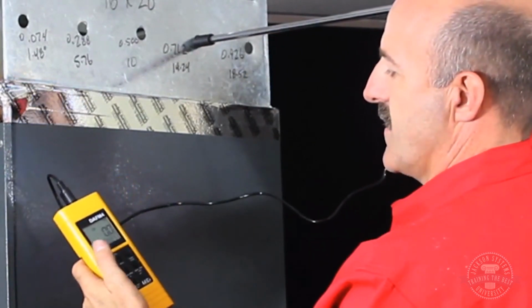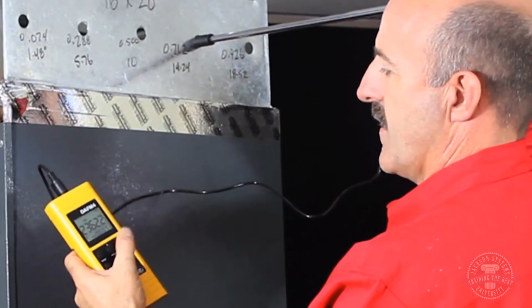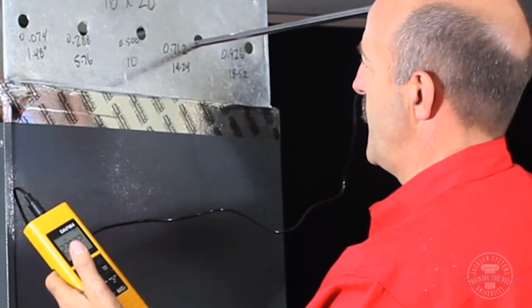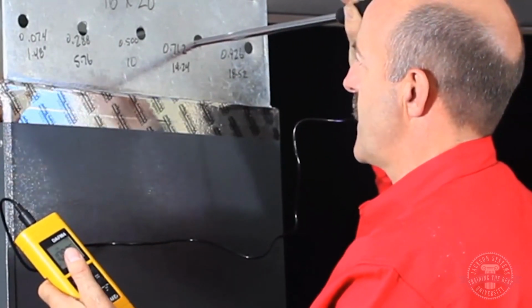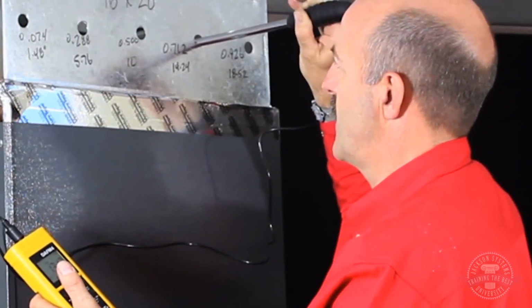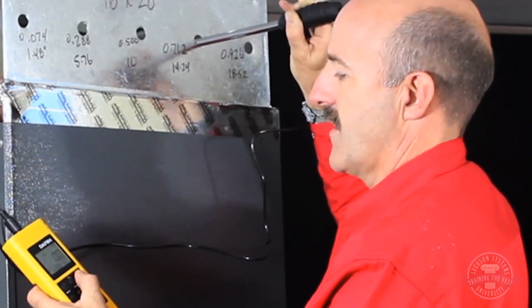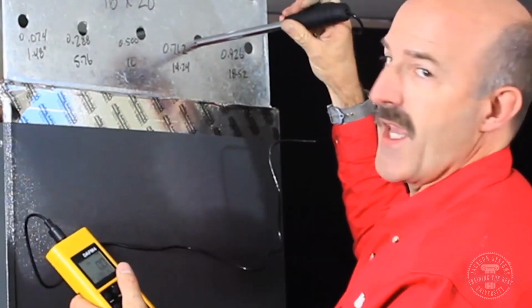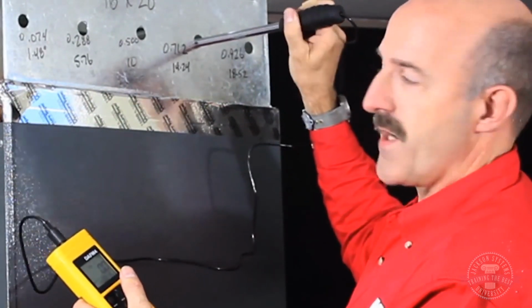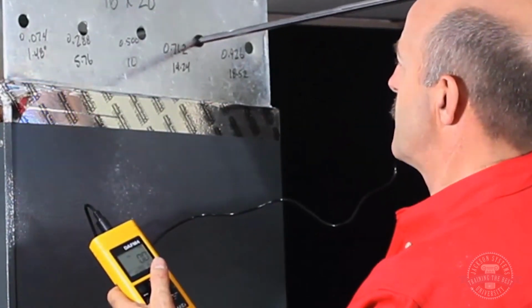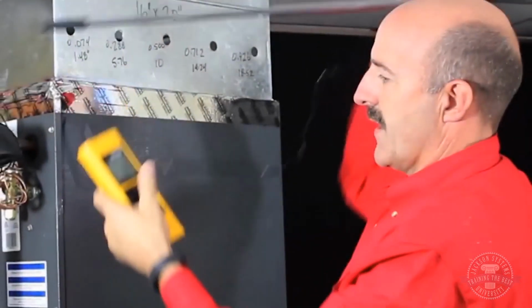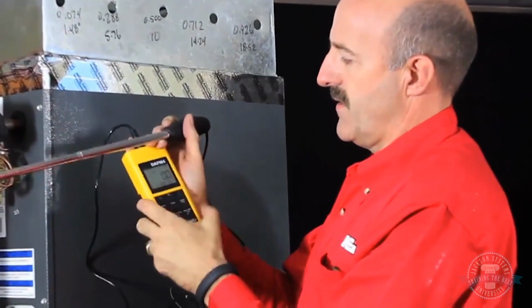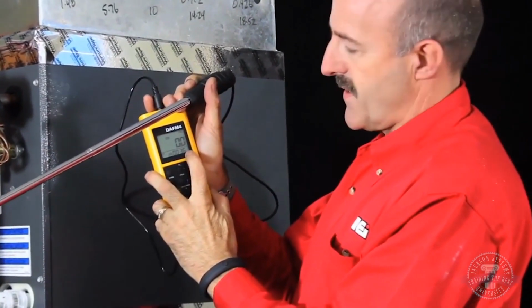I go to the next access hole, I hit start, and I very slowly go across that until I hit the far side, I hit stop. And you'll notice the handle is elongated so you can keep the direction proper. After I have all the measurements taken, my total time is 36 seconds.